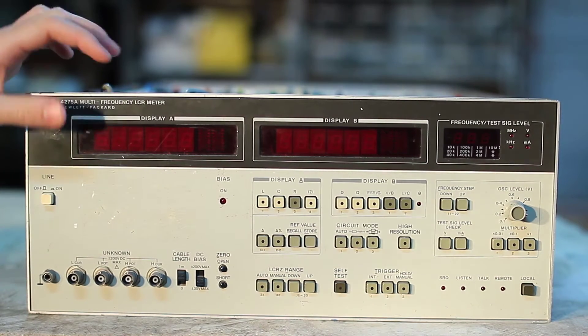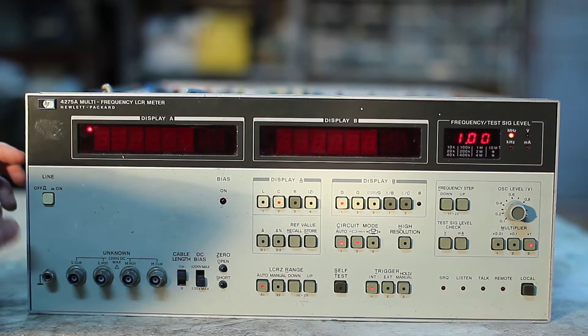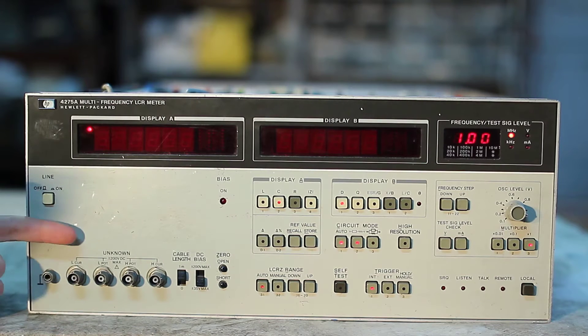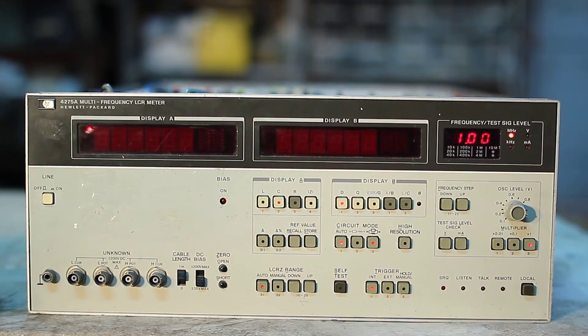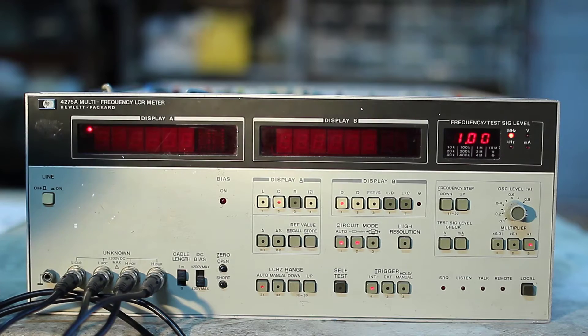Let's power it up and see what happens. It successfully passes all the initial self-test. However, it looks like after the initial settings are completed, the instrument holds and the trigger lamp does not begin flashing. I don't think it's because it's missing a test fixture, but we can connect two BNCs to the input terminals and see if it makes any difference. This is the connection I made with the two BNC cables. The shields are already shorted together inside the instrument, so now it should measure an open circuit. But the problem still persists.